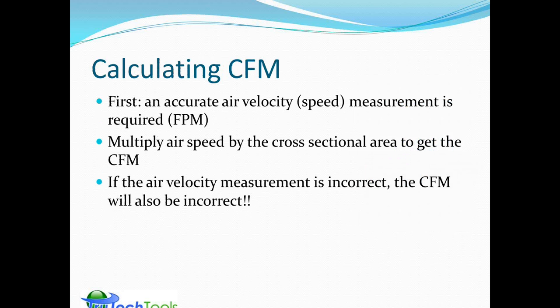In calculating CFM, you first need an accurate air velocity measurement, usually in feet per minute. You multiply that velocity by the cross-sectional area to get cubic feet per minute. An important point: if the air velocity measurement is incorrect, the CFM is also going to be incorrect — there's no way to correct it with another calculation. It's only as good as the air velocity measurement you're making.